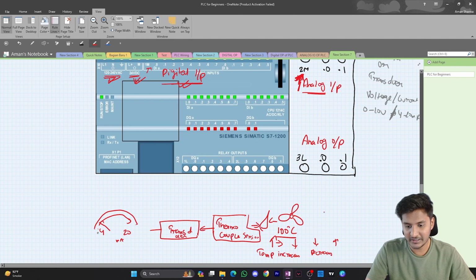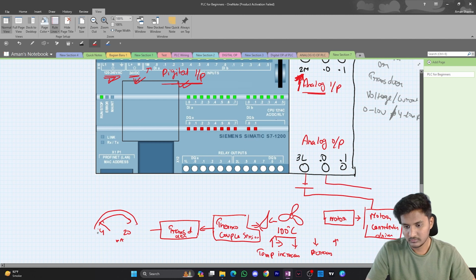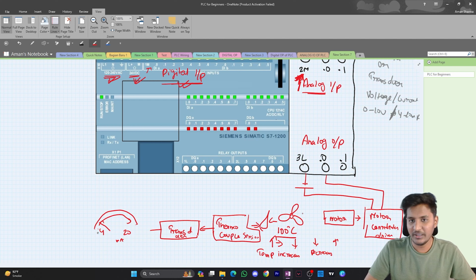So assume that the fan is connected to a motor, and the motor will have a motor controller including a motor driver. So we will give the analog output which will be sent by the PLC as per the temperature to control the speed of the motor, which will control the speed of the fan eventually. So this was a basic example for analog input and output.